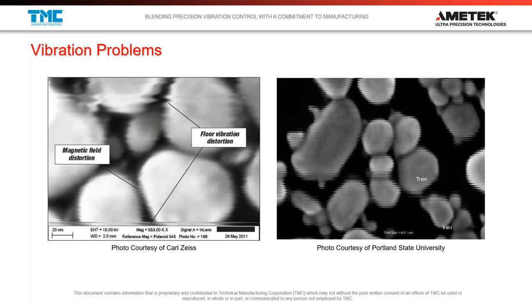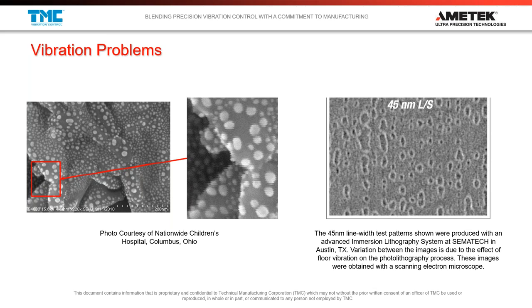How does vibration cause a problem? These are a couple of images from a scanning electron microscope — a test sample of gold particles. You can see ripples and vibrations that are static in the image. That's a telltale characteristic of floor vibration and sometimes magnetic field distortion in an SEM image. Another example from the semiconductor industry shows where straight, even, clear lines were intended, but instead you see a mismatch of dots and mess — all due to floor vibration.